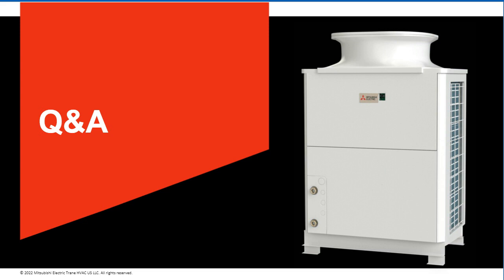Okay. We have a few questions concerning alternative uses for the system, so I'll just combine them. Can the heat pump be used for comfort cooling while providing domestic hot water, and is it possible to also do space heating with the system? No, but there's a product coming in the very near future that will do that kind of thing. I'm sure multiple manufacturers will have it, and basically that's your multi-pass low delta T that you can do radiant floor, you can do space heating, that sort of thing. This product was purpose-built for domestic hot water, so it's a super low GPM, high delta T single pass.